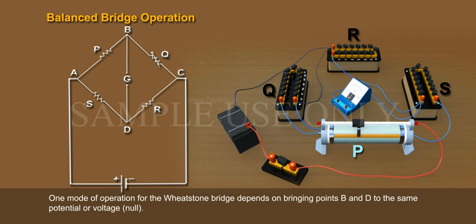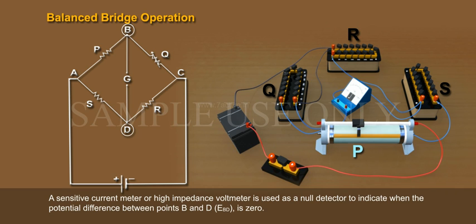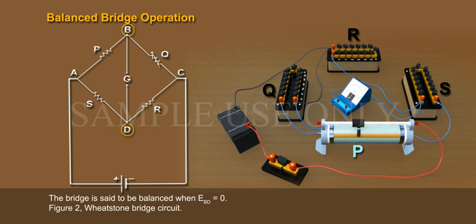One mode of operation for the Wheatstone Bridge depends on bringing points B and D to the same potential or voltage — null. A sensitive current meter, or high-impedance voltmeter, is used as a null detector to indicate when the potential difference between points B and D, EBD, is 0. The bridge is said to be balanced when EBD equals 0.